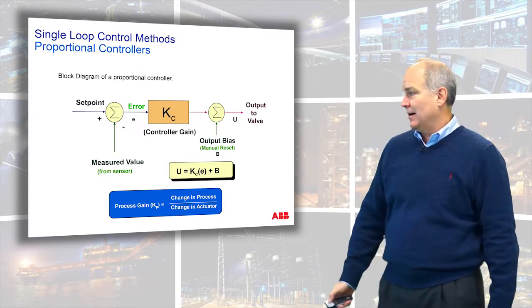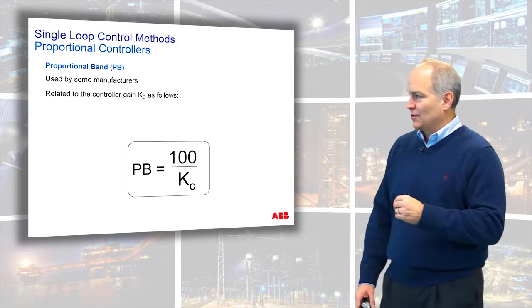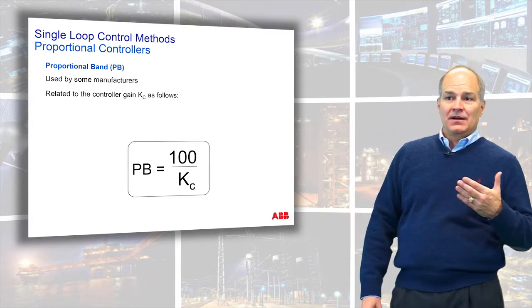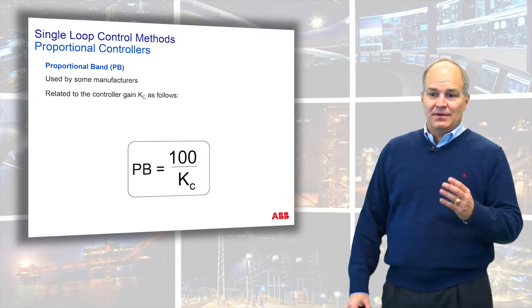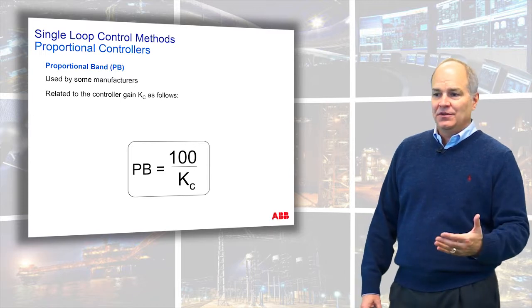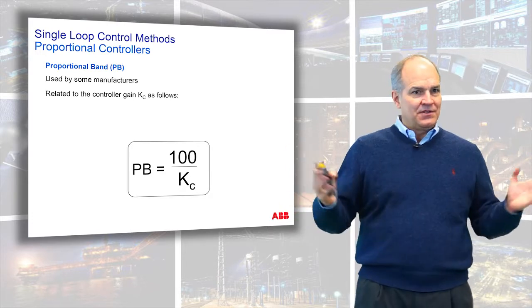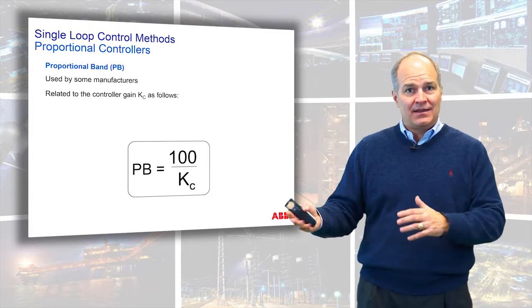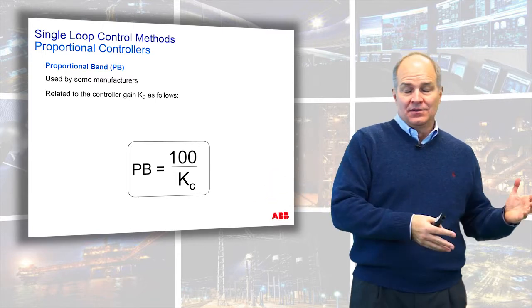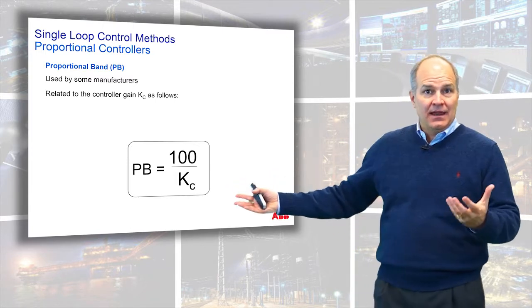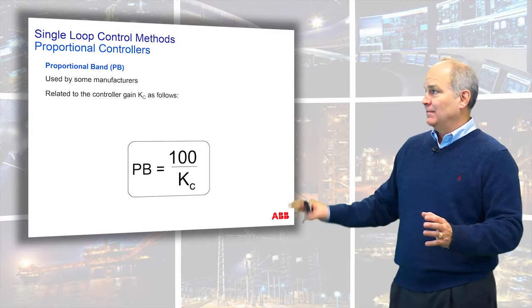Some vendors use the term proportional band. Proportional band and control gain are inverses of each other — for example, a control gain of 0.3 equals a proportional band of 333. I recall talking to an I&E staff member: I said I need a control gain of 0.5 and he said he never used anything other than 200. We were saying exactly the same thing, but he was working in proportional band and I was thinking in control gain.